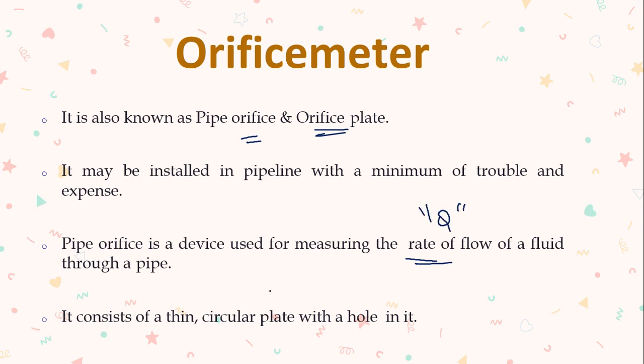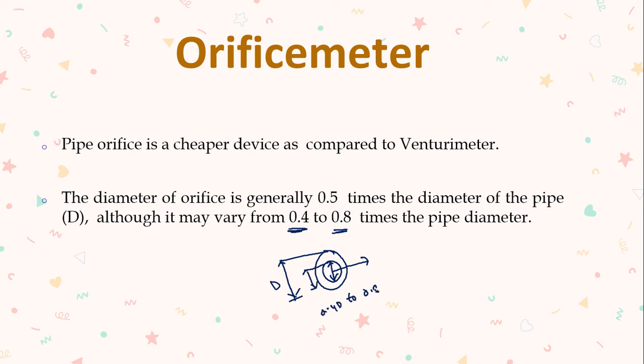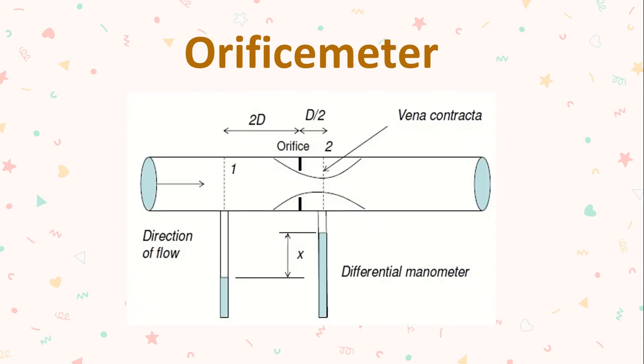The basic component of an orifice meter is a circular plate — this circular plate is what we call the orifice plate, and the inner hole is the orifice. The diameter of this orifice is generally 0.4 to 0.8 times the pipe diameter. So if the pipe diameter is D, the orifice diameter inside is approximately 0.4D to 0.8D. Most of the time we take it as 0.5D — exactly half the pipe diameter.